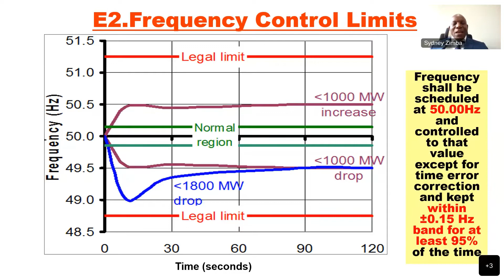So if we lose like only 300 megawatts, the power frequency goes below this point. It's something we investigate because we don't expect that one. We come up with a report and mitigation measures. So we've defined our reserves. We've got instantaneous reserves, regulating reserves, quick reserves, and slow reserves. These terms are from the US. In Europe, they use the primary reserve, secondary reserve, and tertiary reserve. Same purpose, though. So the instantaneous is the one which is localized at our generation plants.